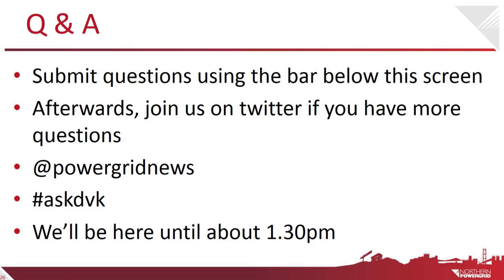Someone's asked about large demands as well as generation. Connected demands and connected generation feed into our calculated maximum and minimum demands for the previous year, but they take a while to come through. Until they've come through in our actual measured demands, we account for them in our contracted figures, making an adjustment for contracted generation that hasn't yet connected. So the headroom figures should reflect how much capacity is left, excluding the quoted jobs I mentioned earlier, and that applies equally for load and generation.